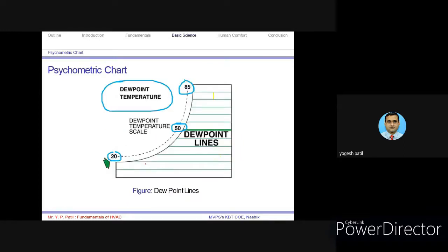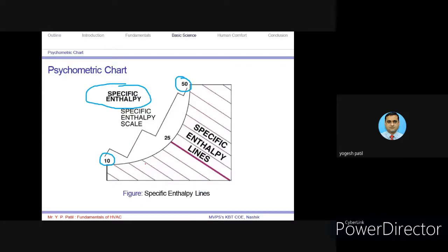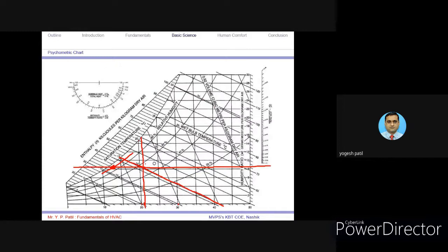Yes, this one, by horizontal lines. Horizontal lines where the relative humidity line crosses. That scale is again the same scale as the wet bulb temperature, no change in the scale. You can see this here. So what will be the temperature of the dew point? This is the 10 over here. So it is greater than 10 and close to 10. I may say 11, 12 like this. So dew point temperature I can say 12 degrees Celsius approximately.